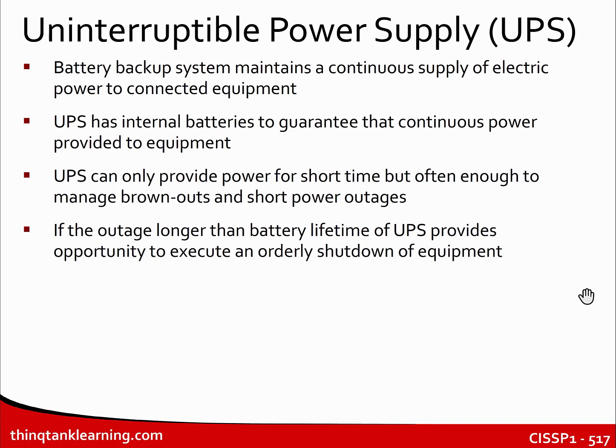One of the issues we have with UPSs is the consumables — batteries lose their ability to store charge over time. A battery that's effective today for 3 or 4 hours of runtime might, in a year, only be effective for about 20 or 30 minutes. Something to consider. But we know what a UPS is — everybody listening probably understands the need for one and its value.